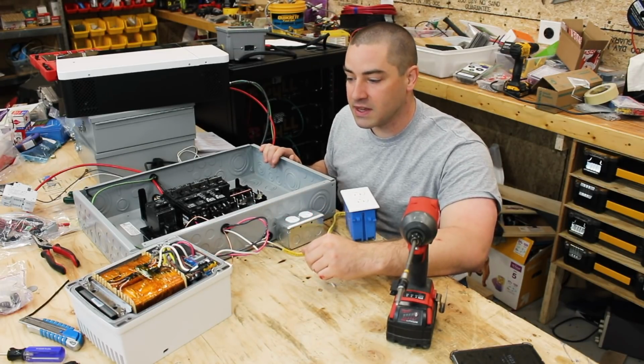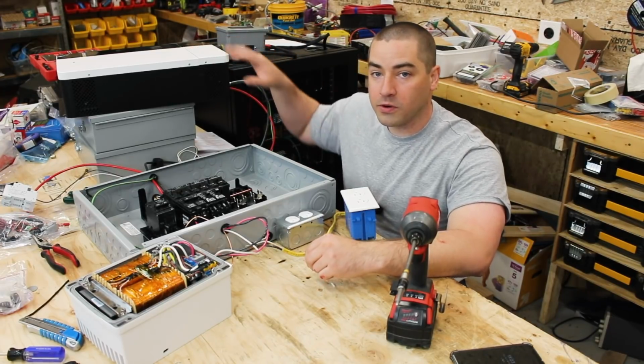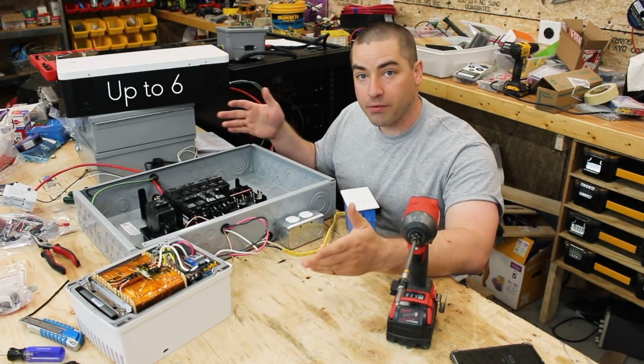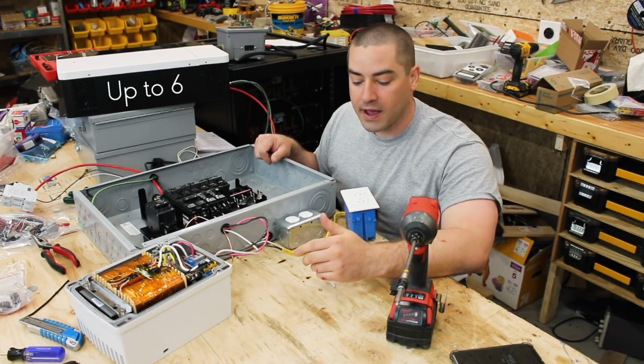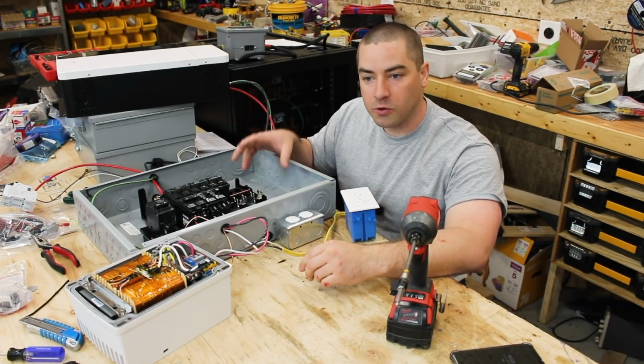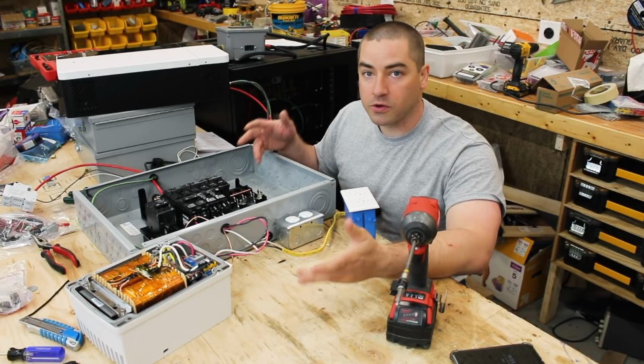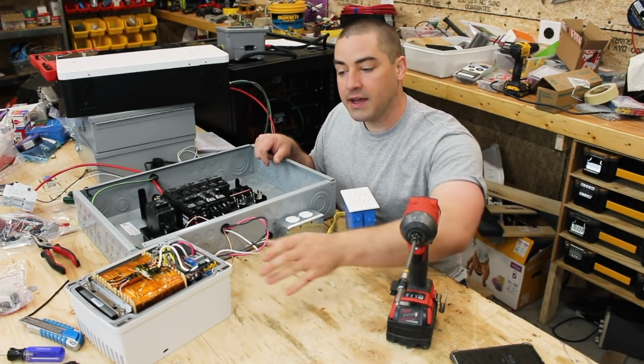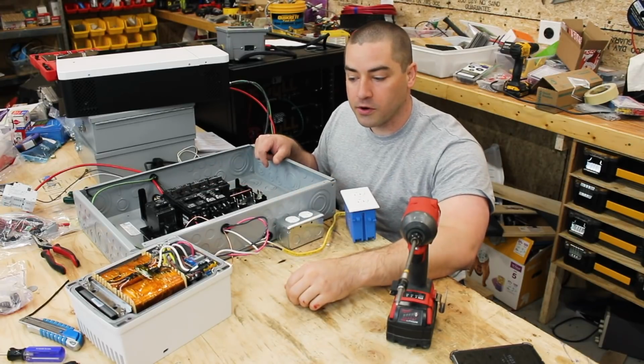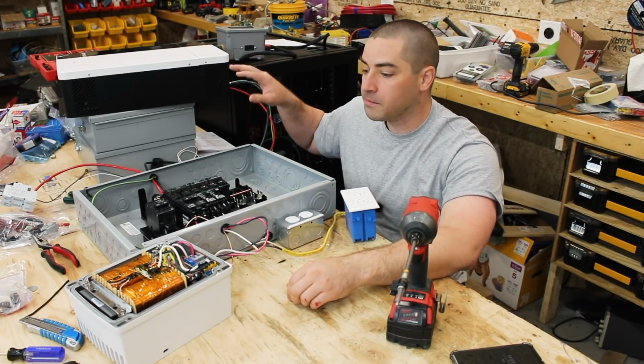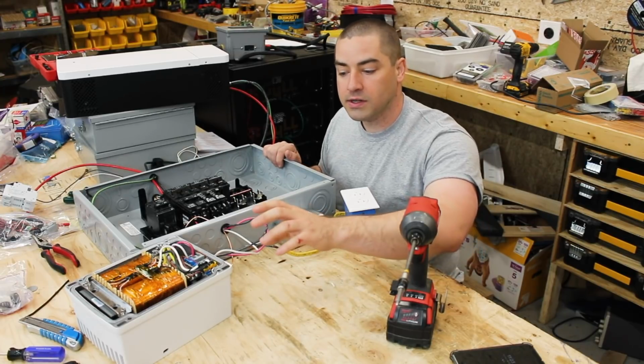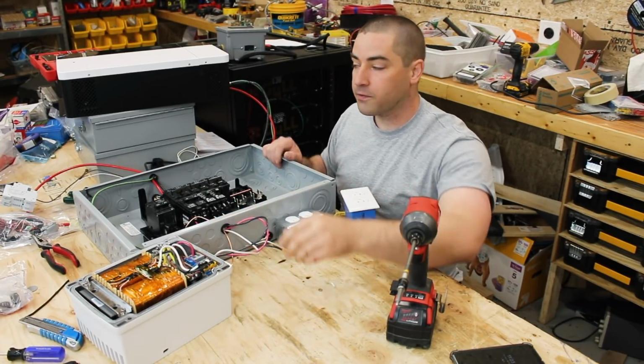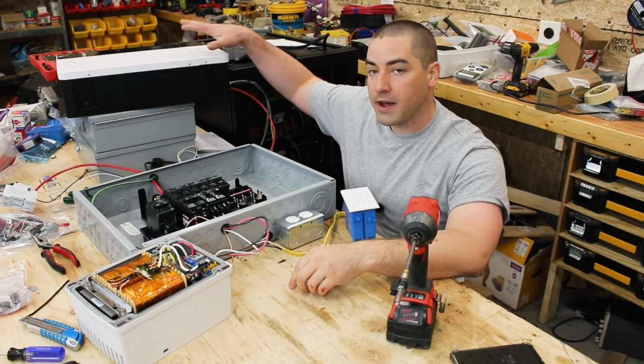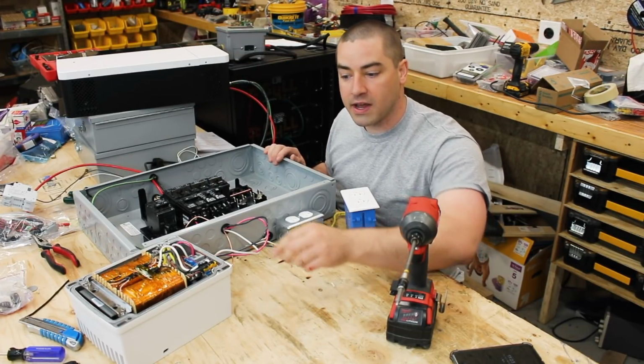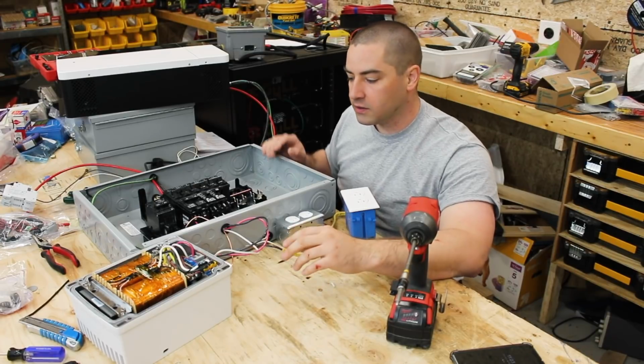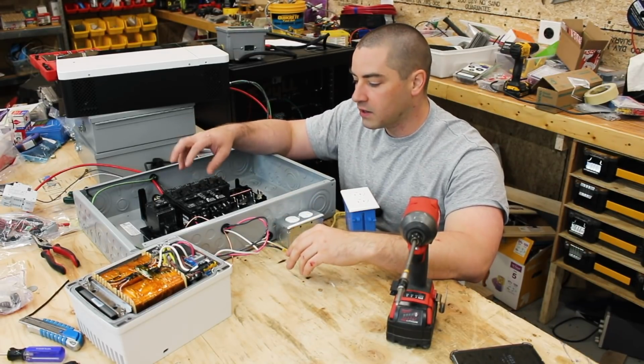Also, what this means is that I can add on one more inverter or two more inverters. I could have three inverters without having to always get matched pairs and go two at a time, as you would if you were doing 120 volt inverters. And this single transformer can handle multiple of these. You don't necessarily have to have one auto transformer for every one inverter. So I could have three of these 5,000 watt inverters and one auto transformer. Now I'll demonstrate why that is coming up here in the video.